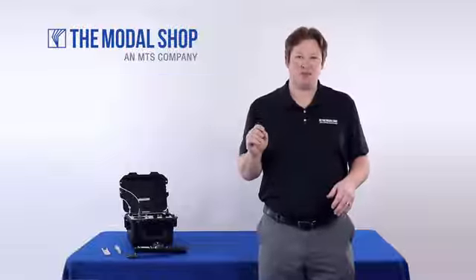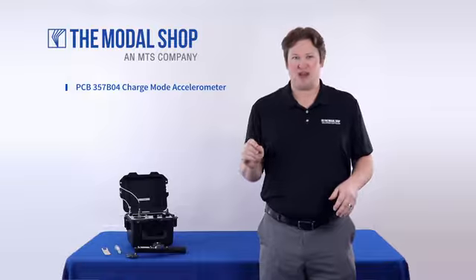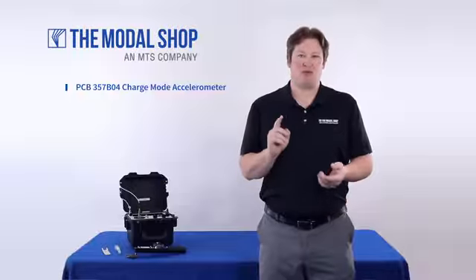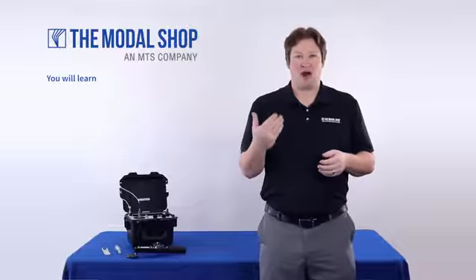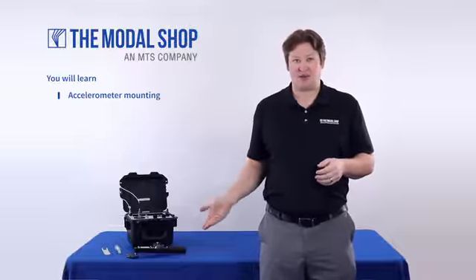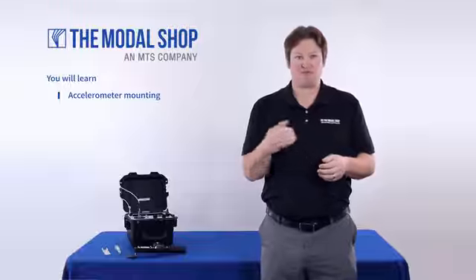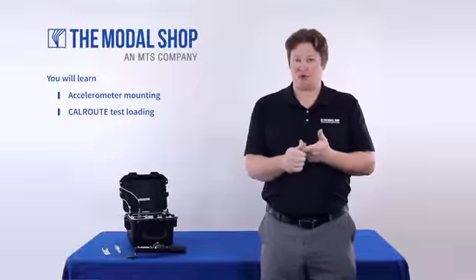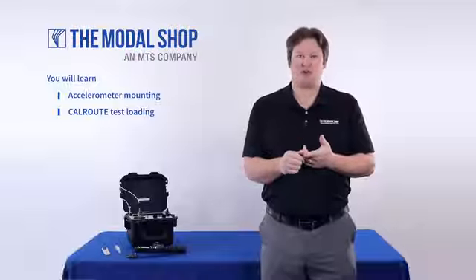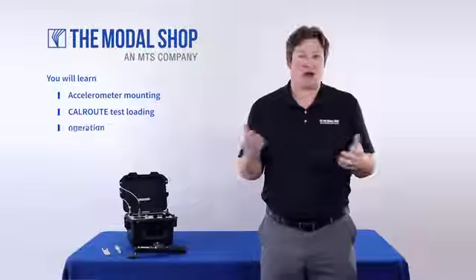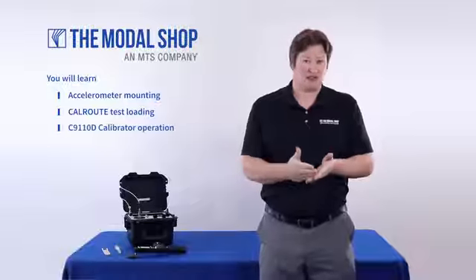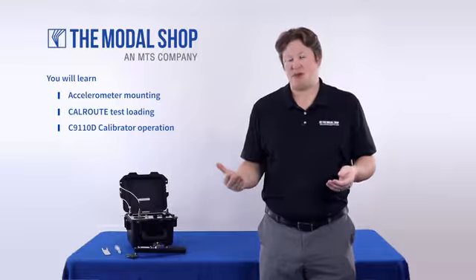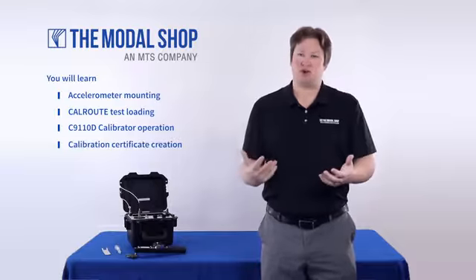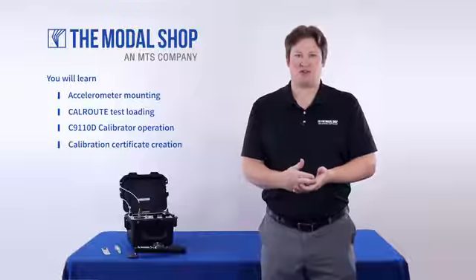We're going to calibrate a PCB 357B04 single-ended 10 picocoulomb per G charge mode accelerometer for the test and measurement market with a plus or minus 5% tolerance to 9 kilohertz. In this video, you will learn how to mount the transducer and connect it to the C9110D portable vibration calibrator, how to load a CalRoute, which is a programmed step sine test with a pass-fail notification after each test point, how to operate the C9110D and execute the test, saving the test points to the memory, and how to create a calibration certificate as well, and we'll show the finished calibration certificate.